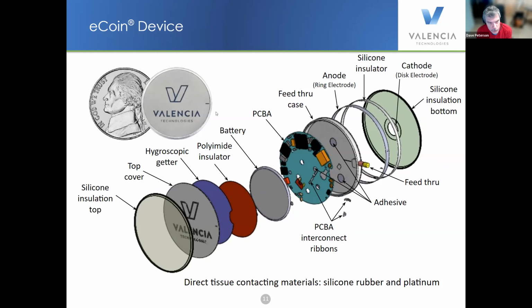As I said, it uses a lithium battery. Because it's hermetically sealed and you're using organic materials inside the device, although we bake out the materials and pull the moisture out before we seal it, there's always residual moisture and outgassing. So we put a hygroscopic getter in the device that's designed to stabilize the moisture inside of it over the life of the unit. And as I said, there's a single feed through.